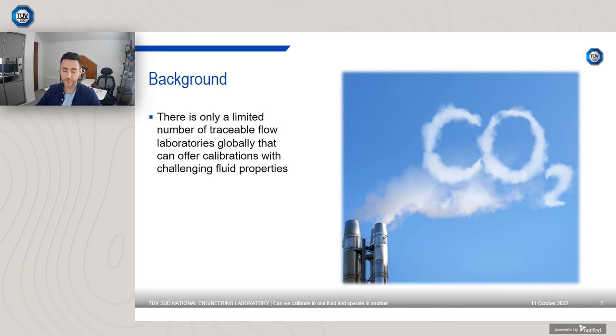measurement. So just now there's still a question as to whether we need to build these new facilities for gas CO2 and liquid CO2, or can we potentially calibrate in water, which is readily available in a lot of calibration laboratories, or nitrogen gas, for example, again freely available in a lot of calibration laboratories, and then use them in CO2 with a higher uncertainty. So for example, calibrate in water at ambient conditions and then use them at elevated conditions with a completely different fluid, CO2, what kind of uncertainty would you expect?